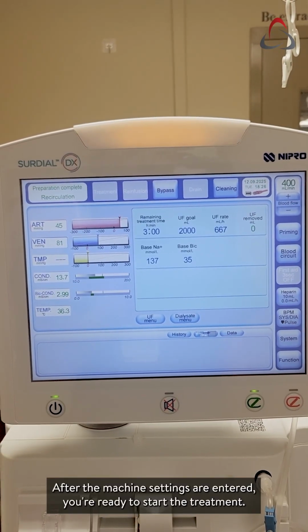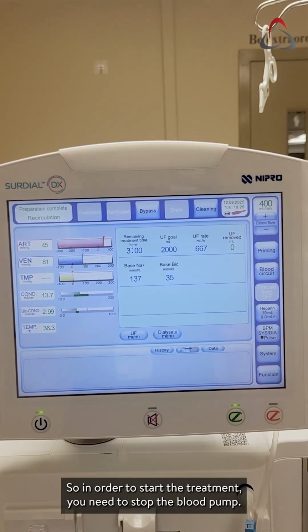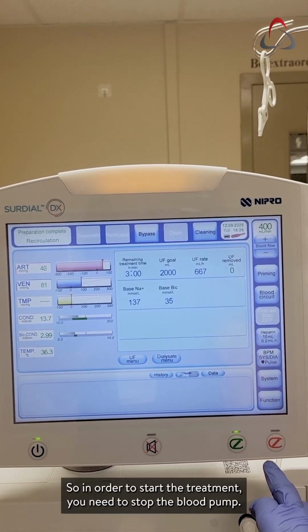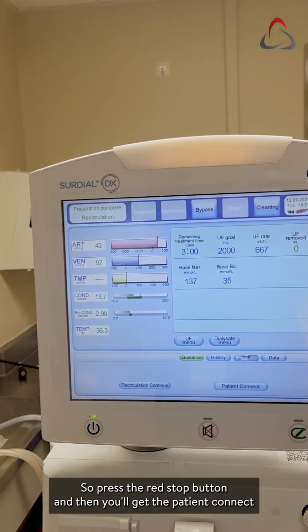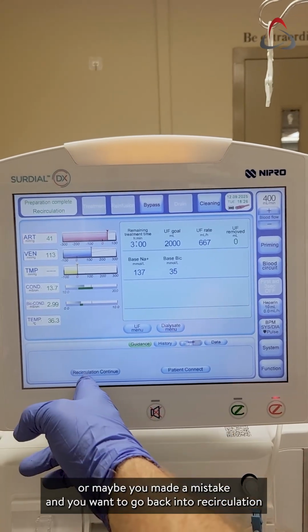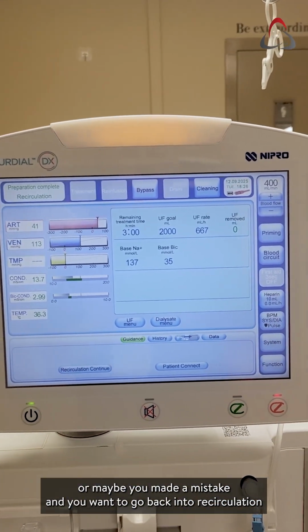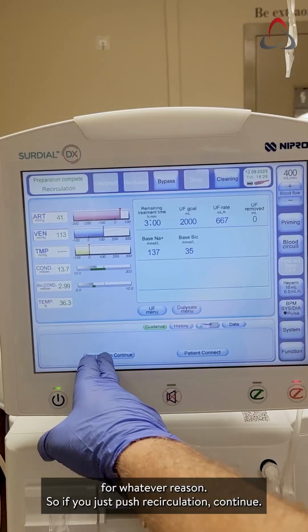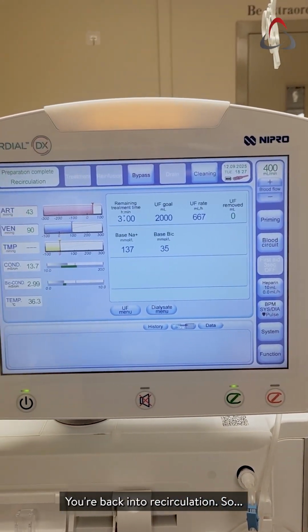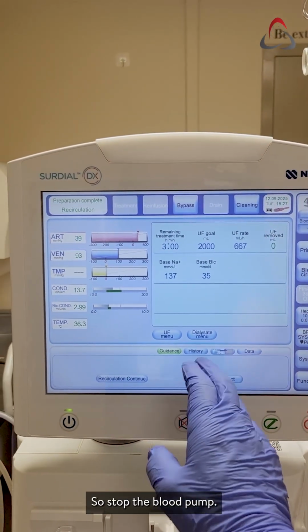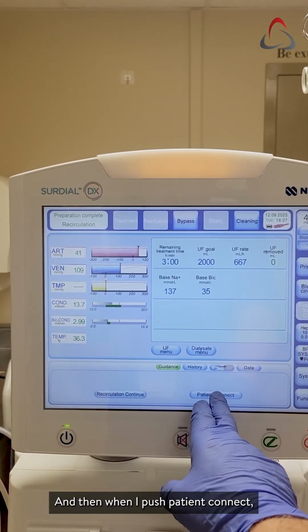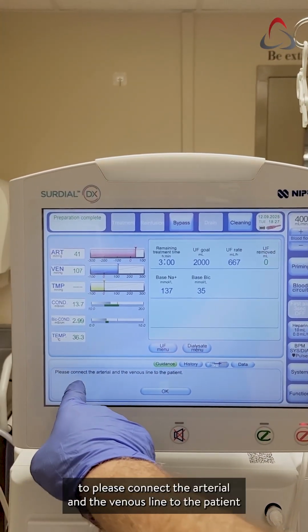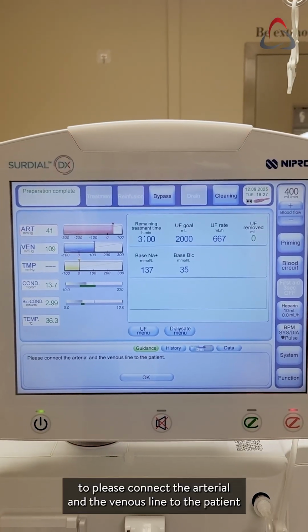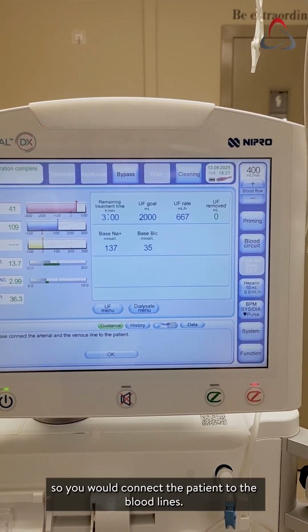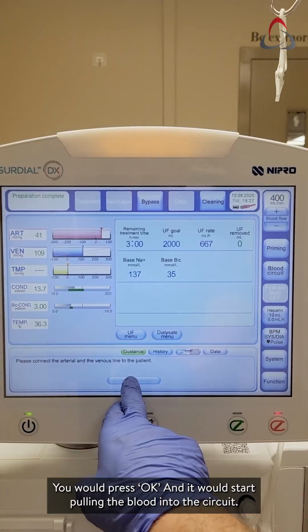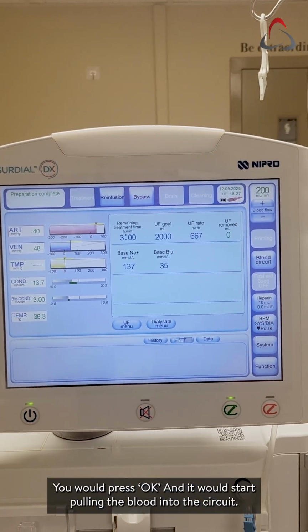After the machine settings are entered, you're ready to start the treatment. So in order to start the treatment, you need to stop the blood pump. So press the red stop button, and then you'll get the patient connect, or maybe you made a mistake and you want to go back into recirculation for whatever reason. So if you just push recirculation continue, you're back into recirculation. So stop the blood pump, and then when I push patient connect, it tells you to please connect the arterial and the venous line to the patient. So you would connect the patient to the blood lines. You would press OK, and it would start pulling the blood into the circuit.